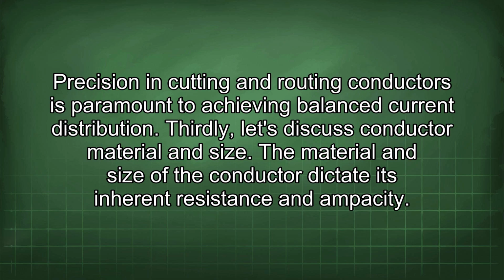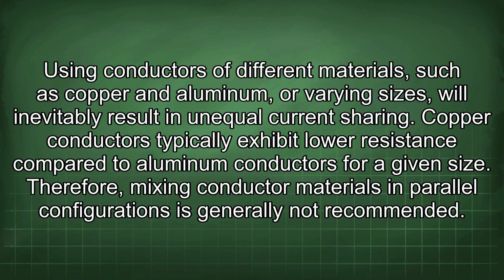Thirdly, let's discuss conductor material and size. The material and size of the conductor dictate its inherent resistance and ampacity. Using conductors of different materials, such as copper and aluminum, or varying sizes, will inevitably result in unequal current sharing. Copper conductors typically exhibit lower resistance compared to aluminum conductors for a given size. Therefore, mixing conductor materials in parallel configurations is generally not recommended.